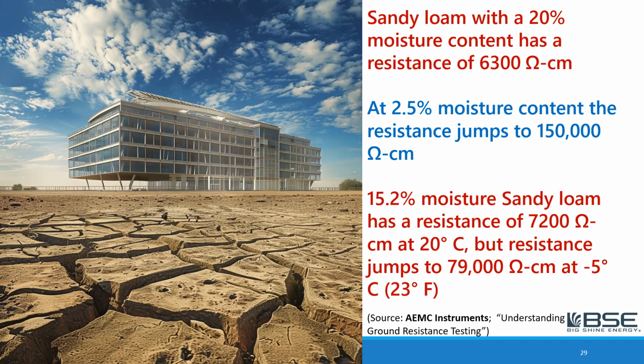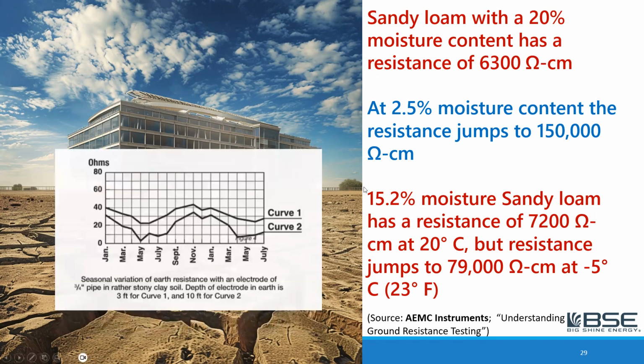So also temperature is a big factor. If you have a nice 15.2% moisture sandy loam and has a resistance at 20 degrees Celsius, what we would call roughly about room temperature, 7,200 ohm centimeters, what does it do when it's cold at 23 degrees Fahrenheit or -5 Celsius? It jumps to 79,000. So it means that if we measure the resistance of our grounding system at one time of year and under one set of climate conditions, if we measure it months later, it may be totally different.